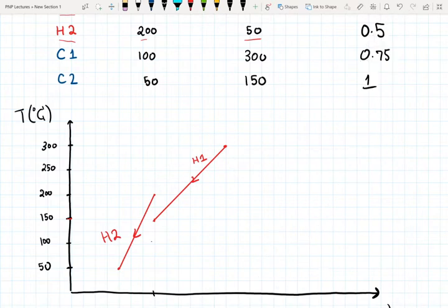What we want to do is look for intervals where these streams cross temperatures. If you look at the interval 200 and 150, in this interval you encounter both of the streams. So what we want to do is combine the streams that occur in the same temperature interval and make one single composite curve instead of two individual temperature enthalpy curves.